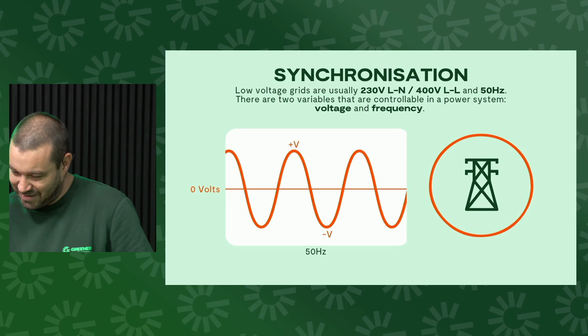But when we needed to synchronize a battery to the grid, obviously the battery, when it's in its grid-forming mode itself, in order to get that to synchronize, it needs to transition to then follow that grid. So it needs to match its voltage and its frequency to do so, and it does that by measuring the angle difference between the two sinusoids - it measures the difference in timing.